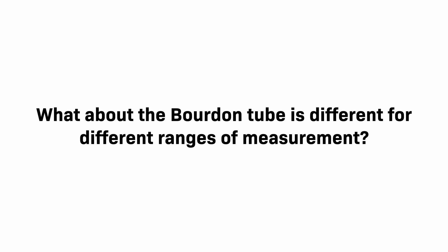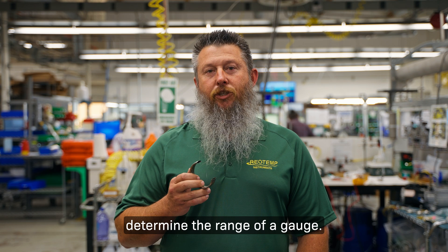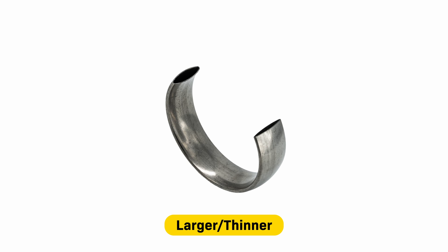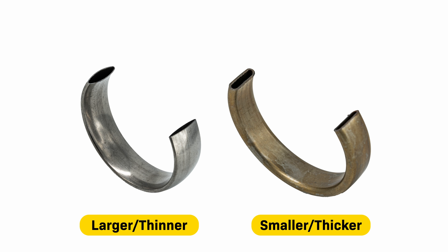What about the Bourdon tube is different for different ranges of measurement? A Bourdon tube's size and wall thickness determine the range of a gauge. Larger, thin-walled tubes are used to measure lower pressures. Smaller, thicker-walled tubes are used to measure higher pressures.